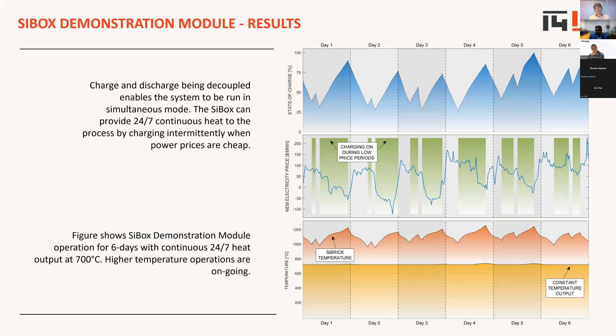The unique thing is that the control system selects periods of low prices on the grid. The blue curve is the actual electricity spot market price in South Australia during these periods, and you can see it charges during low price periods. Some of these are even negative price events, which happen quite regularly in South Australia. South Australia has one of the highest renewable penetrations in the world, about 70% on average throughout the year, so we get a lot of fluctuation in electricity prices. We have the capability to utilize these low price periods, typically when renewable generation is high, to charge the system and then deliver output continuously.